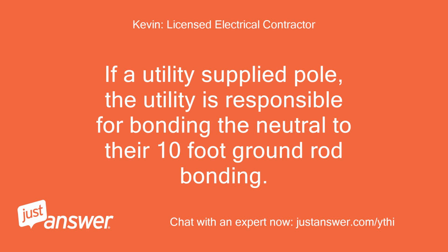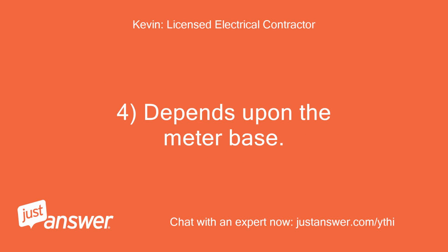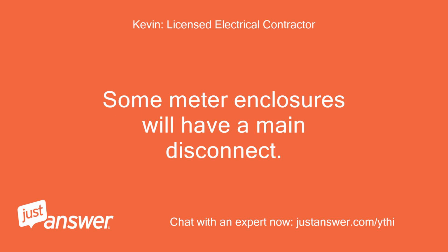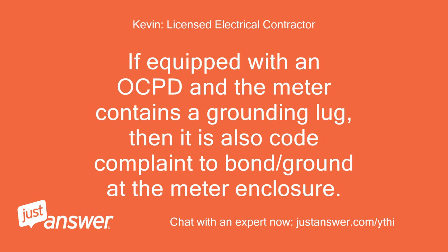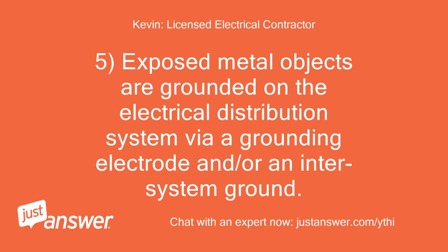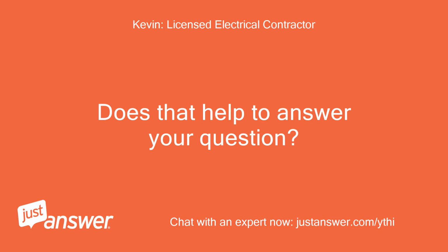If it is a utility supplied pole, the utility is responsible for bonding the neutral to their 10-foot ground rod. 4. Depends upon the meter base. Some meter enclosures will have a main disconnect. If equipped with an OCPD and the meter contains a grounding lug, then it is also code compliant to bond/ground at the meter enclosure. 5. Exposed metal objects are grounded on the electrical distribution system via a grounding electrode and/or an inter-system ground. Does that help to answer your question?